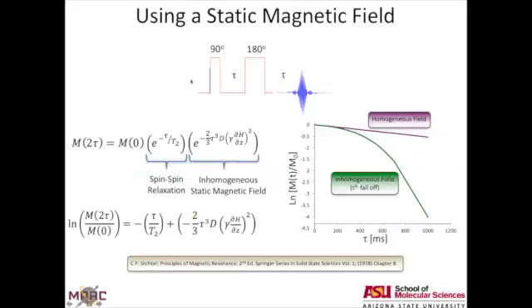And so obviously everyone in this audience knows that if you put a single molecule in solution and it's in one magnetic field, it has one frequency. If you apply a field gradient, you get a distribution of that frequency. And so what I'm plotting on the right is simply what happens when you change the linear X, Y, or Z shim and you're able to produce these profiles where we can exploit that static field gradient to actually measure diffusion. Yeah, and this shows it very clearly. When you're doing just kind of basic spin echo type experiments it falls off exponentially with T2. And that's how you would often, even a spin echo is how you would measure the transverse relaxation time or T2 in a system. But what often gets left out because you usually have your sample shimmed, it's in a homogeneous field. So we don't even show this term most of the time. But if you purposely take the X, Y, or Z1 shims, the linear gradients that all magnets have associated with them so that you can shim or get homogeneous and purposely make it inhomogeneous or linear static gradients, then you can reintroduce this term, which falls off cubically in time and use that to measure the diffusion coefficient just by creating a static linear gradient with a shim coil.